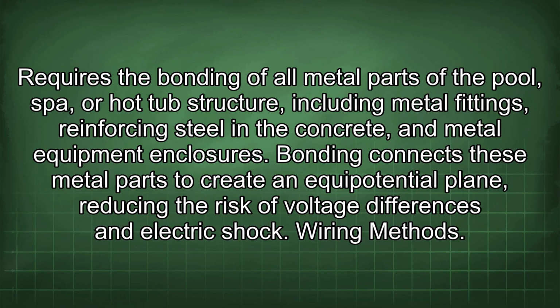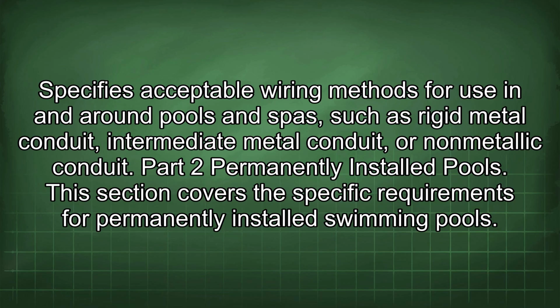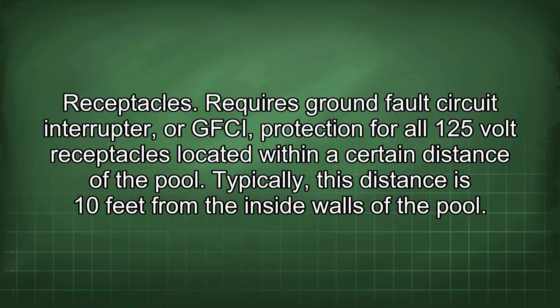Wiring methods. Specifies acceptable wiring methods for use in and around pools and spas, such as rigid metal conduit, intermediate metal conduit, or non-metallic conduit. Part 2, Permanently installed pools. This section covers the specific requirements for permanently installed swimming pools. Receptacles. Requires ground fault circuit interrupter, or GFCI, protection for all 125-volt receptacles located within a certain distance of the pool. Typically, this distance is 10 feet from the inside walls of the pool.